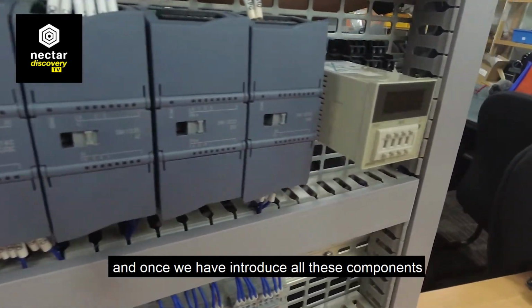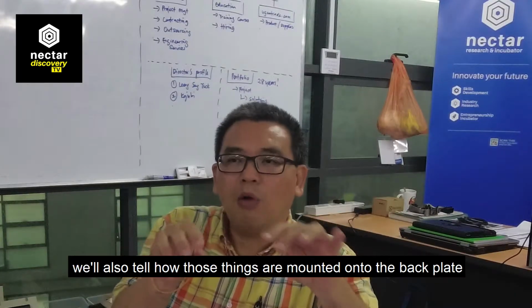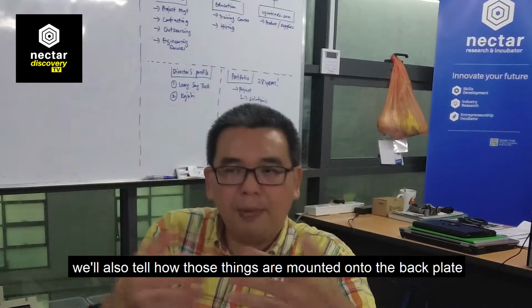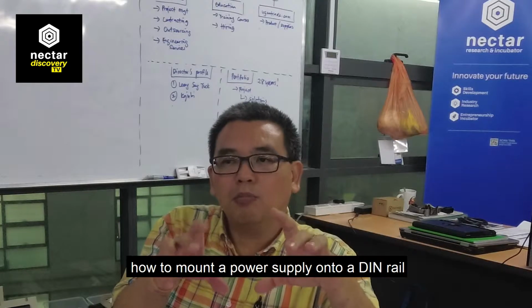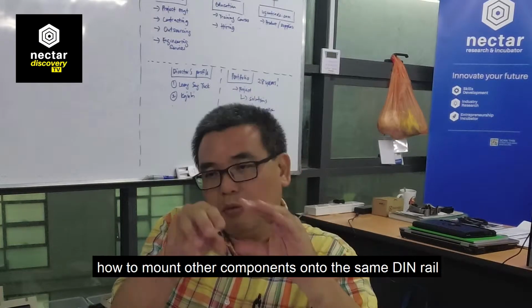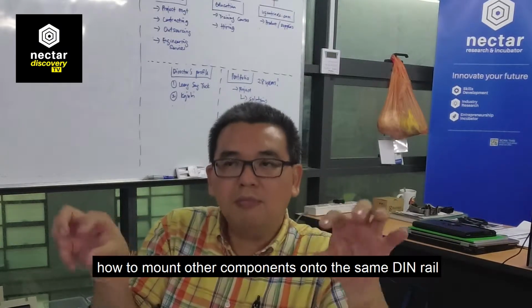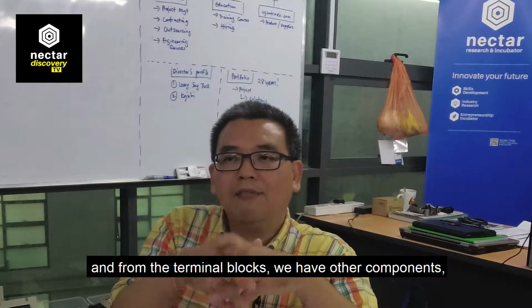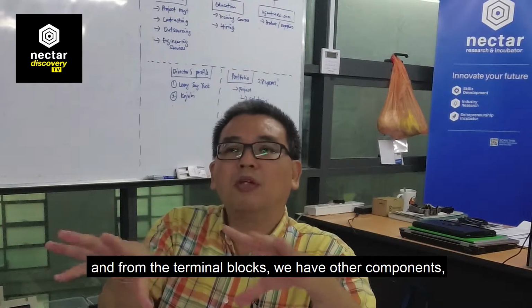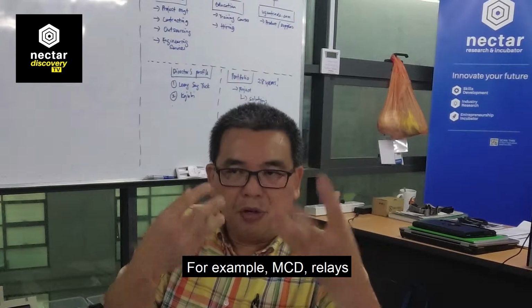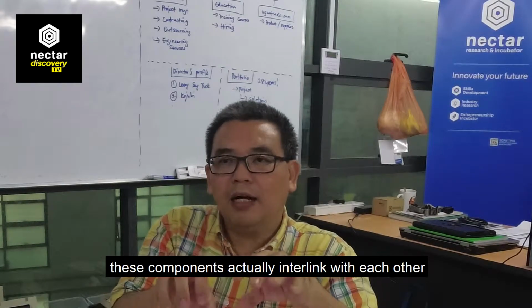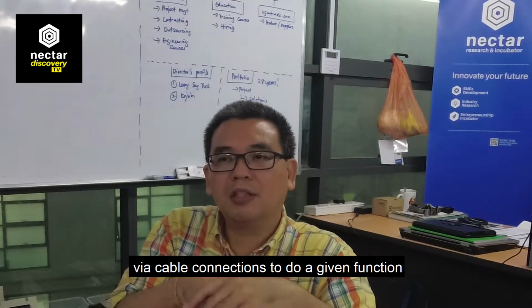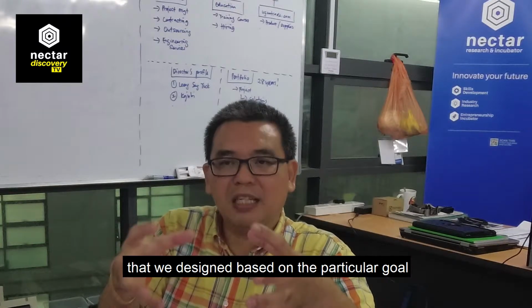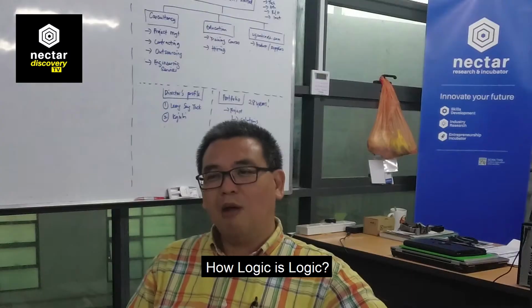And once we have introduced all these components, we also tell how those things are mounted onto the backplane. We teach step by step, for example, how to mount a power supply onto a DIN rail, how to mount other components onto the same DIN rail, for example, terminal blocks. And from the terminal blocks, we have other components, for example, MCB, relays. These components actually interlink with each other via cable connection to do a given function that we design based on that particular goal. How logic is logic.